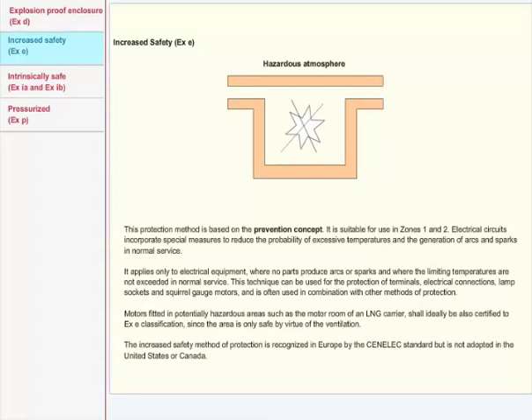Increased safety, Ex e. This protection method is based on the prevention concept. It is suitable for use in zones 1 and 2. Electrical circuits incorporate special measures to reduce the probability of excessive temperatures and the generation of arcs and sparks in normal service. It applies only to electrical equipment where no parts produce arcs or sparks and where the limiting temperatures are not exceeded in normal service. This technique can be used for the protection of terminals, electrical connections, lamp sockets, and squirrel cage motors, and is often used in combination with other methods of protection.